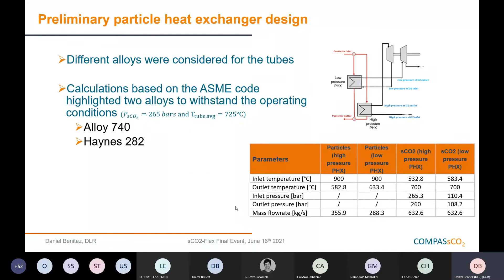So first we work on the selection of state-of-the-art alloys. We can find Inconel 740 or Haynes 282, for instance, that can withstand them. Based on that, let's say a preliminary design has been done of a heat exchanger for a commercial application. We have noticed that it would be, of course, a very large component with more than 60 tons of Inconel 740 with 30.8 millimeter thickness tubes. This, of course, has a high impact on the cost. We are also, of course, thinking on combining with lower cost materials for lower temperatures at the bottom of the heat exchanger. But at least for the top design, we have the top of cost design.